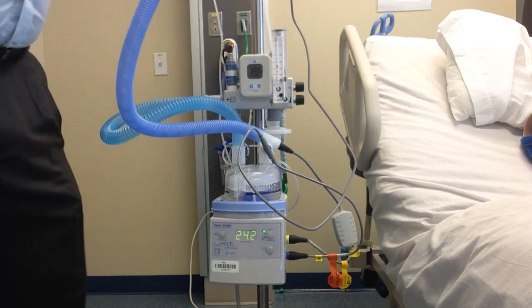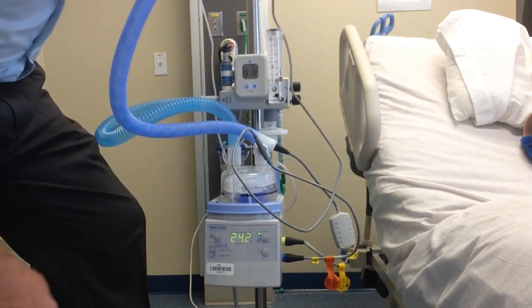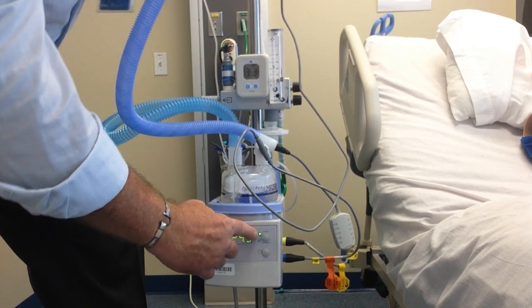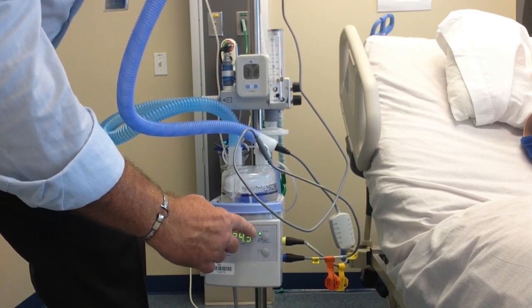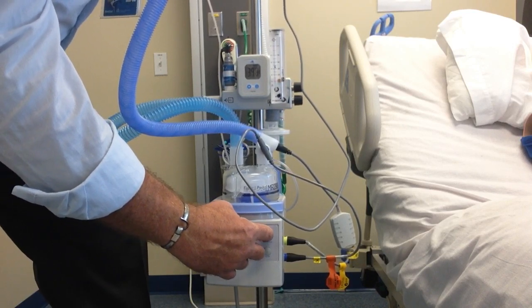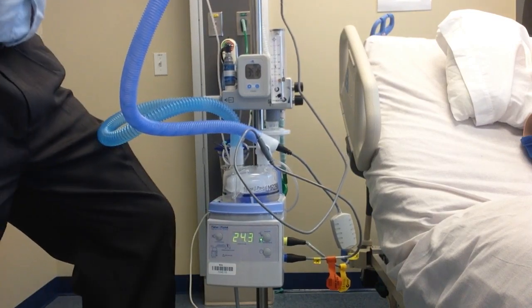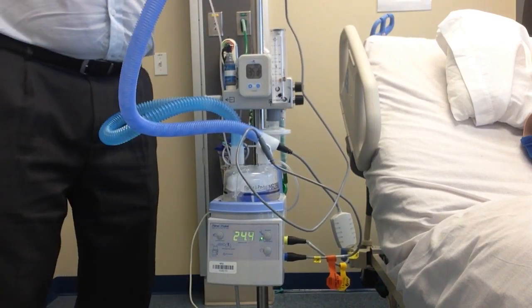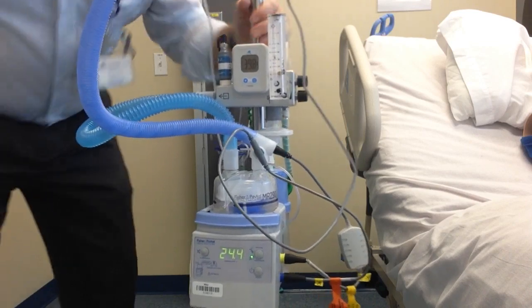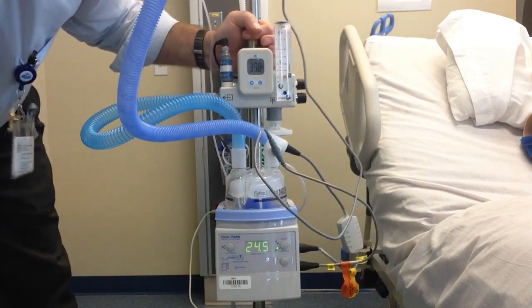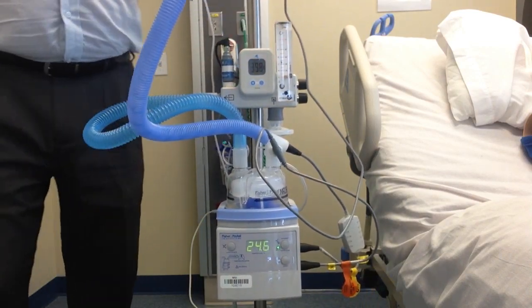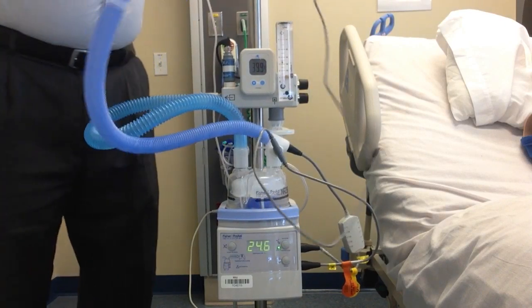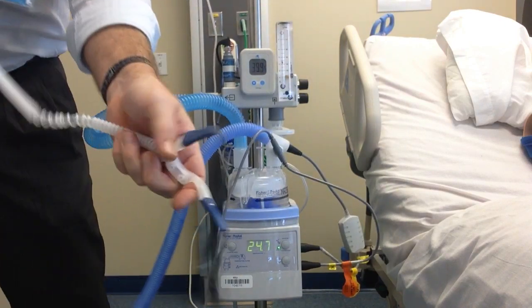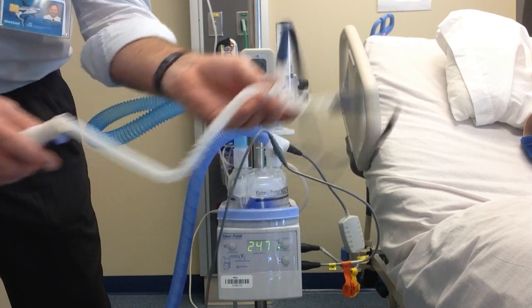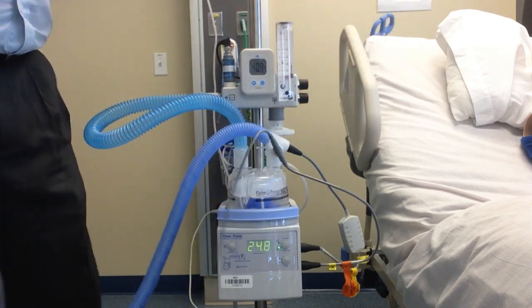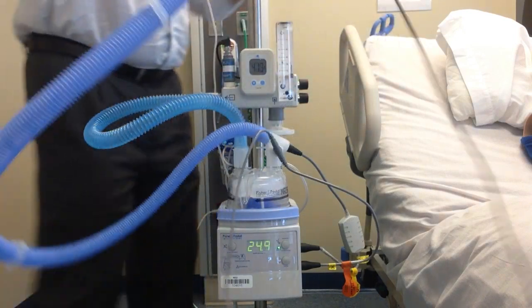It'll also alarm when your temperature is too high, too low, or you're out of water. Right now, there's two lights here. We'll go over it in more detail a little bit. You have invasive and non-invasive. We want non-invasive. It causes a lower temperature, more comfortable to the patient. Okay. We're running at 39.8% oxygen, 40 liters per minute. I have my patient interface here. It's running. Eventually this will get warm enough, nice and toasty on a non-invasive.